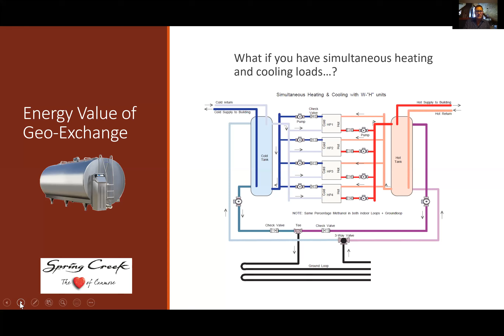So for instance, we're running air conditioning in the summer. We can also take the heat that's generated and, instead of sending it to the field, send it to a preheat tank for our hot water. So you want your hot water at 160, but we can preheat the water coming in from the street up to 110 degrees while the air conditioning is running. Then the 110-degree water can be taken up to the appropriate temperature you need for hot water for the house. So there are major advantages to GeoExchange and to using the system simultaneously, in that we're not wasting that heat in air conditioning mode when we can use it to heat up our hot water or heat up the other side of the building that might be cold. And we use that in all my major buildings to make them more efficient.